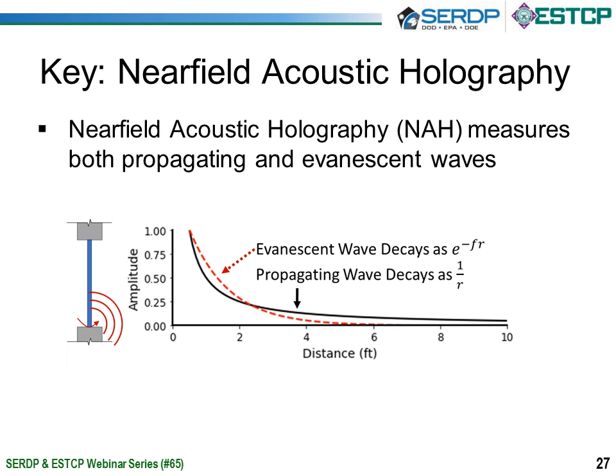When you're really, really close to the source, though, there's another type of wave called evanescent. These decay exponentially, and it's not just related to the distance, it's also related to frequency. So low frequency sounds will have a longer decay distance than the higher frequency sounds. So if you have low frequency sounds like we use with SonicLQ and we're close to the wall, we can measure both propagating waves and the evanescent waves. And those two things together let us do a lot more computation and get more information about the sound. It lets us actually separate sound that's from a crack or a leak from sound that's coming through vibration. And then we can compute the overall size of the leak.